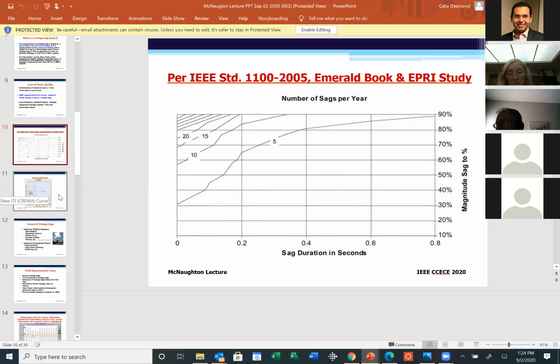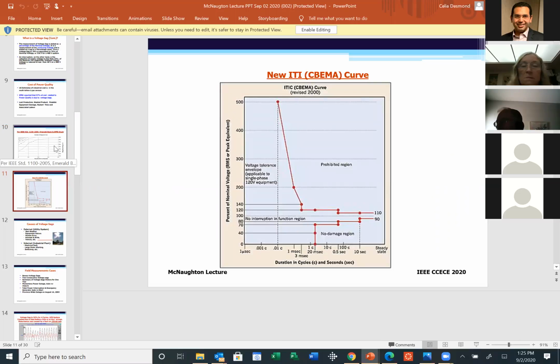This graph was developed years ago by the computer guys. More or less, it shows that if you look at the x-axis, where it starts from 1 microsecond, I don't think you can see my mouse. Can you see my mouse? Not really, no. If you look at the x-axis from 1 microsecond to about 20 milliseconds, that red one, basically what this is telling us is that when there is an event, if it is between these red horizontal lines to the left, that equipment is supposedly able to operate and continue functioning. But if that event results in a voltage drop to the right and below it, then that equipment might malfunction.